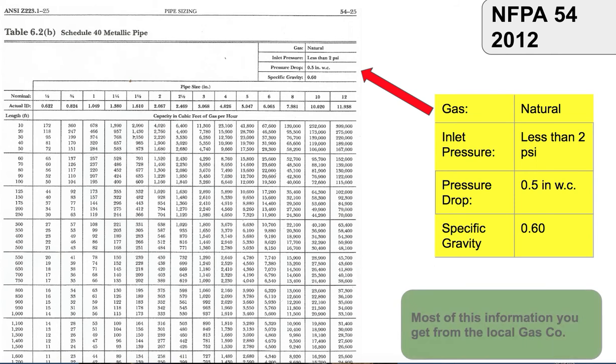You can get some of the other characteristics — some of this information — from your local gas company. They can provide you information regarding pressure and specific gravity of the gas. 0.6 is pretty common for natural gas specific gravity, but you always want to double check with your local gas supplier.